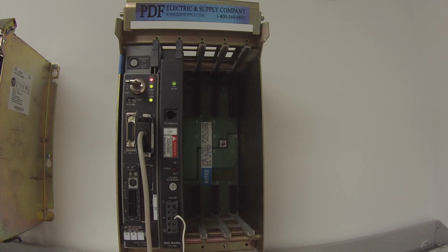So again, if this is a troubled processor, this would be a good place to start to see if there's any problems, what they are, what the codes are. If it seems like the description is something minor, and it's something that I understand what it is, I would probably hit clear major error and clear that out. And then you might want to go through processor warning, which is the next tab, program warning, channel warning, and so on, just to take a look that everything's in the condition it should be in. So once that's done, it's okay to go ahead and test the Ethernet side.